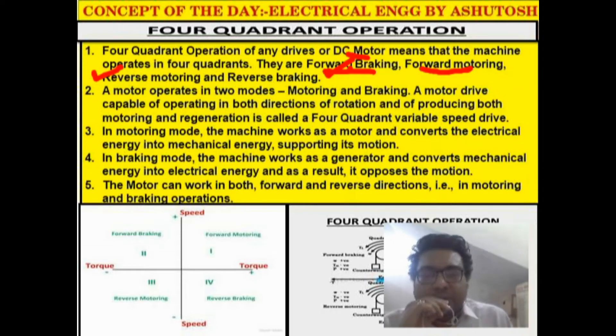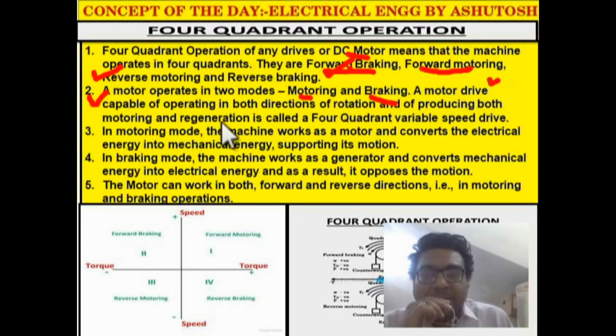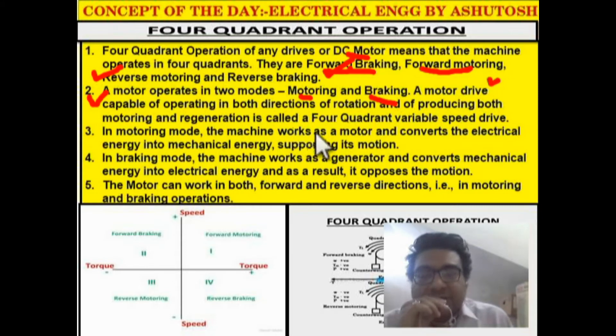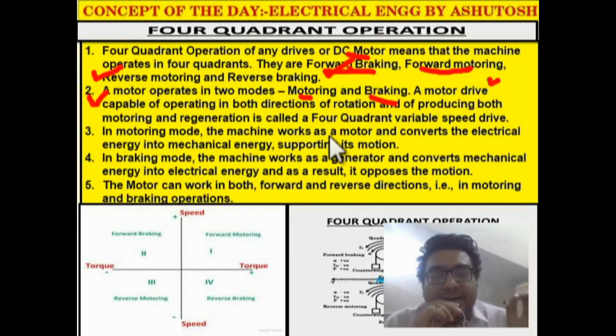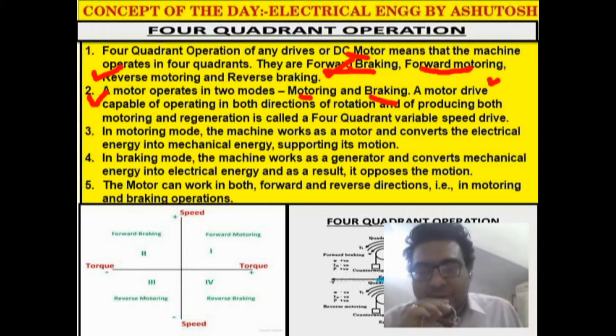A motor operates in two basic modes: motoring mode and braking mode. A motor drive capable of operating in both directions of rotation and producing both motoring and regeneration is called a four quadrant variable speed drive.